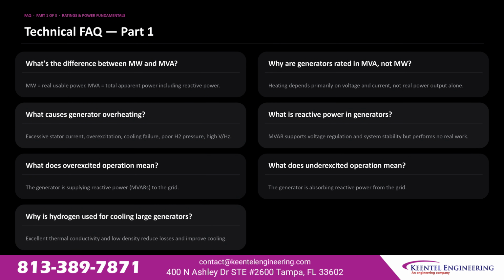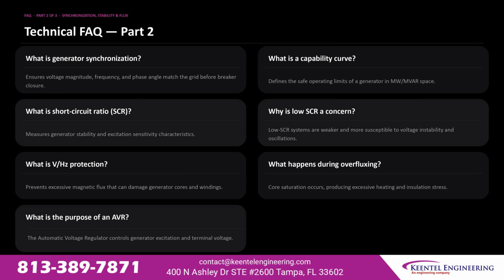What does overexcited operation mean? The generator is supplying reactive power to the grid. What does underexcited operation mean? The generator is absorbing reactive power from the grid. Why is hydrogen used for cooling large generators? Excellent thermal conductivity and low density reduce losses and improve cooling. What is generator synchronization? It ensures voltage magnitude, frequency, and phase angle match the grid before breaker closure. What is a capability curve? It defines the safe operating limits of a generator in megawatts and megavars space.